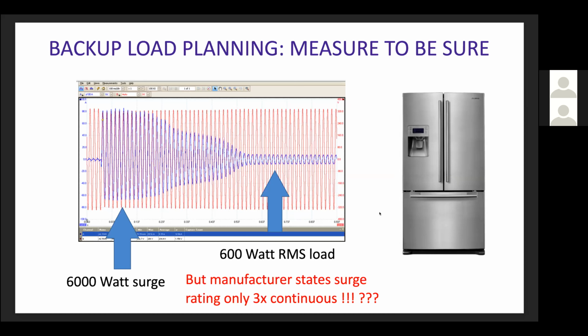To illustrate that point for backup load planning: measure to be sure. This is from an O-scope measurement taken in the lab from a refrigerator our product manager had access to. Don't expect everyone to have an O-scope or a data scope in the field, but this is just to illustrate the point. The manufacturer's nameplate rating is shown here, where the manufacturer stated that the surge rating is only 3 times continuous. But in this case, as shown here, the surge was actually 10 times the continuous load. Whether that was an old refrigerator or needed servicing for some reason, looking at the manufacturer's nameplate is not going to serve you well in all cases. So again, measure to be sure.